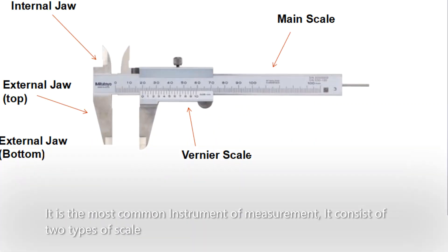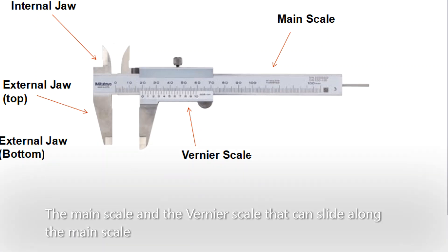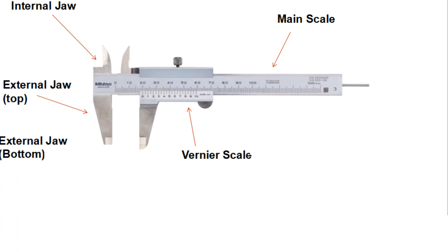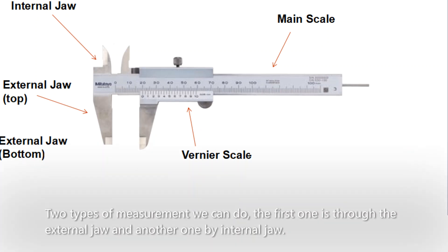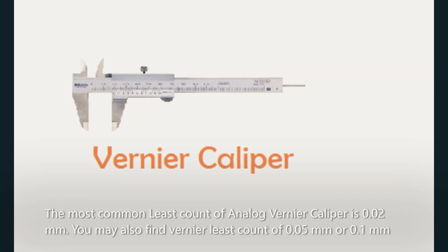The Analog Vernier Caliper is the most common instrument of measurement. It consists of two types of scales: the main scale and the Vernier scale that can slide along the main scale. The measurement can be carried out in two ways — through the external jaw, which measures external dimensions, and through the internal jaw, which measures internal dimensions. The most common least count of Analog Vernier Caliper is 0.02 mm.